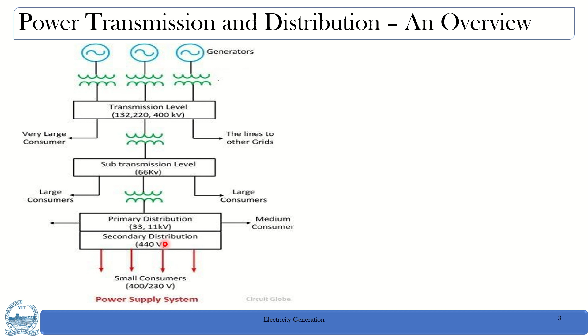In primary distribution, the distribution voltage levels will be 33 kV and 11 kV, and the consumers who are tapping power at 33 and 11 kV are referred to as medium power consumers. Educational institutes and small industries come under this category. Next is the secondary distribution, at 440 volt three phase supply. This is for domestic consumers and small consumers, such as small scale industries, who receive power at 440 volt for three phase and 230 volt for single phase.